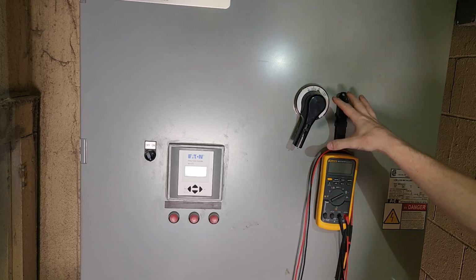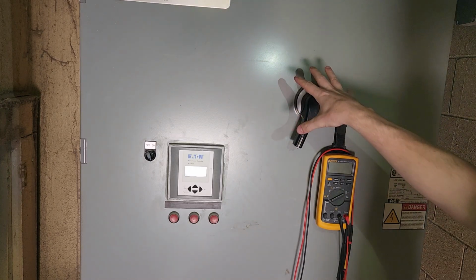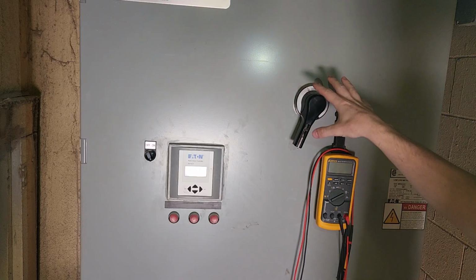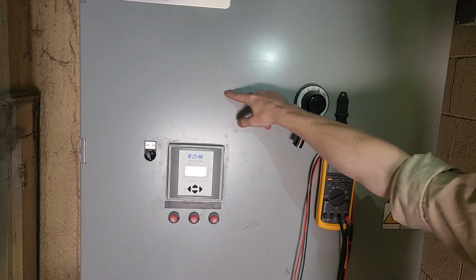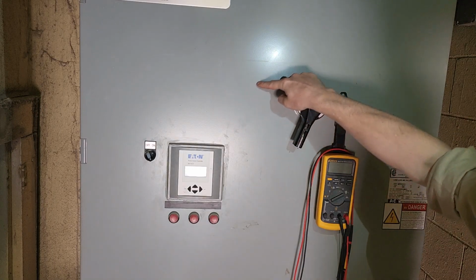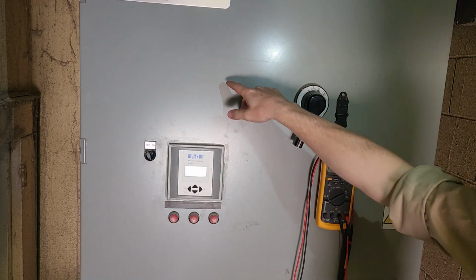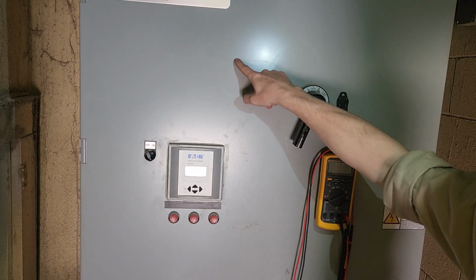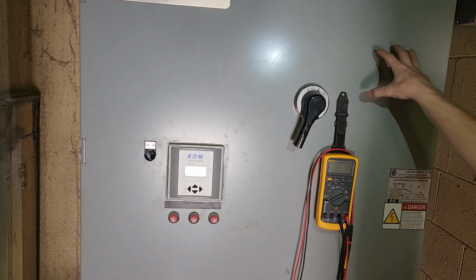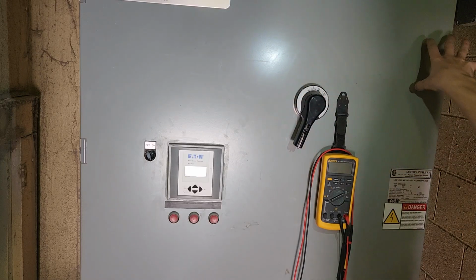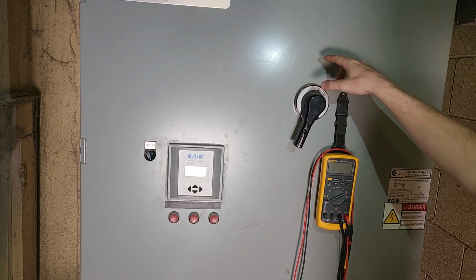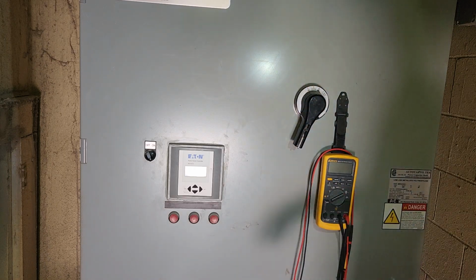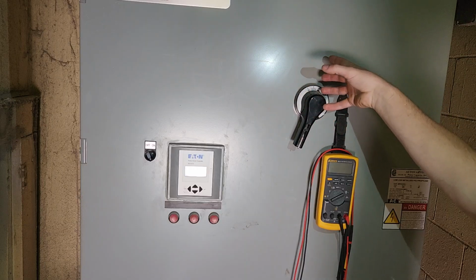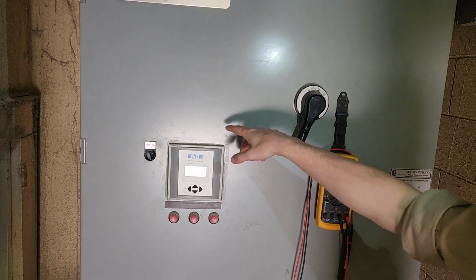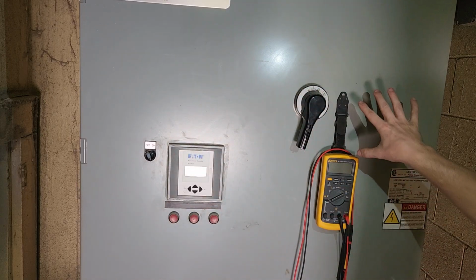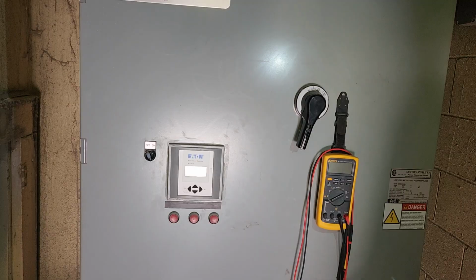Most of you guys probably don't know what this thing does. It's a medium-sized industrial facility. We've got a lot of induction motors. In induction motors, your voltage curve and your amperage curve should be right in line, in phase. But if you have a lot of induction loads, you'll pull your current out of phase with your voltage. An inductive load pulls it one way, and a capacitive load pulls it the other way. So as we turn on more and more induction motors, we turn on more and more capacitors in this bank to make sure our voltage and our current stay in phase with each other, and that helps with our electrical bill.